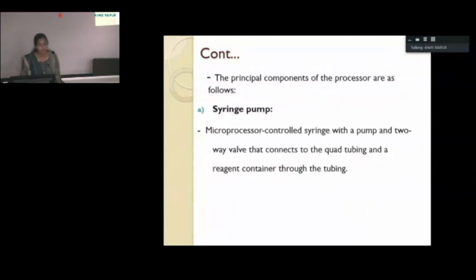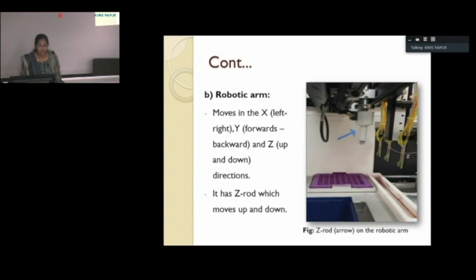Now this robotic processor has several parts. First is the syringe pump, which is a microprocessor controlled syringe with a pump and a two-way valve that connects it to the quad tubing and reagent container through the tubing. Then it has a robotic arm. This arm moves in X, that is left and right, Y, forward and backward, and Z, that is up and down directions. And it has a Z rod which moves up and down. The disposable tip is also located on the top of this Z rod.